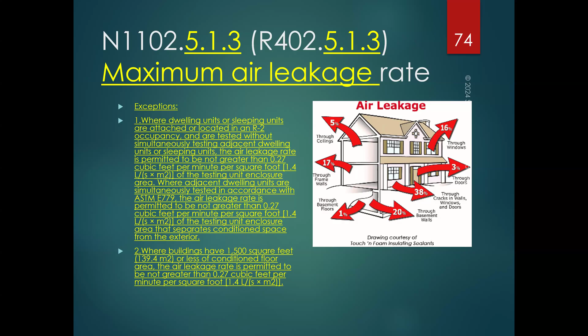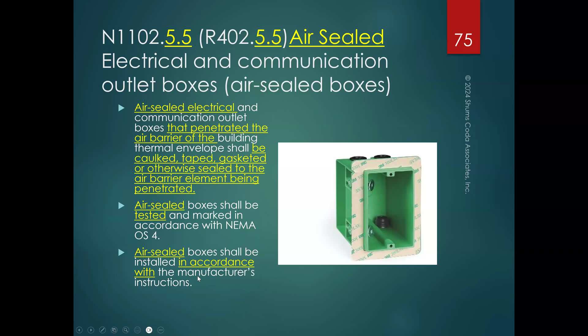All right, so air sealed electrical and communication boxes. This is where the engineers will need to call out and specify an electrical box that will work with the vapor retarder and the other things you've got in your home. They're called air sealed electrical boxes now, and communication boxes, and where they penetrate the air barrier, they have to be caulked, taped and gasketed. They have to be tested and marked within NEMA OS4. The NEMA OS4 requirement was new in the 2021 code, and they just expounded on it in the 2024 code. And they have to be installed, obviously, per manufacturer's instructions. Pretty simple, pretty straightforward, right?